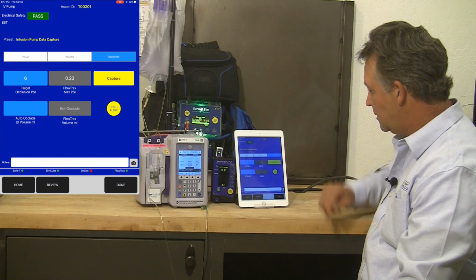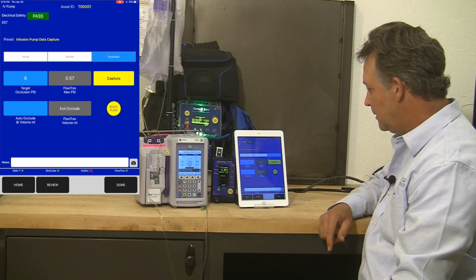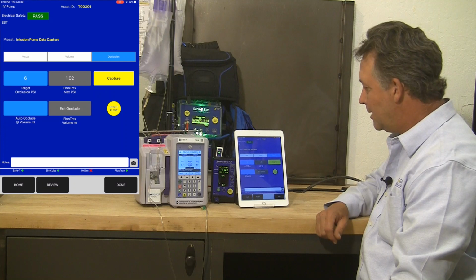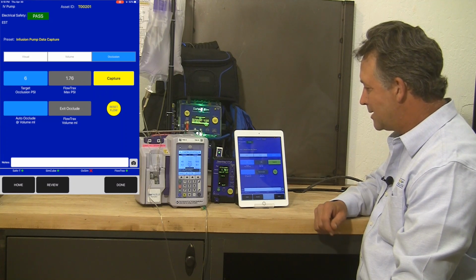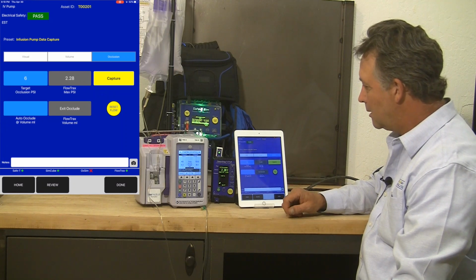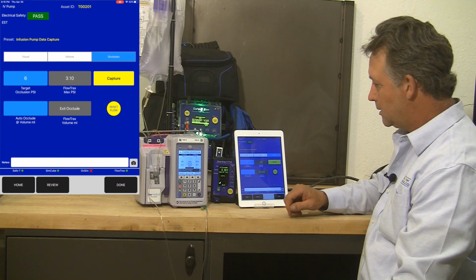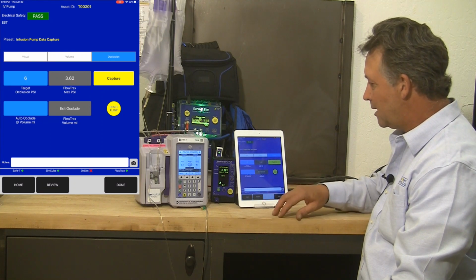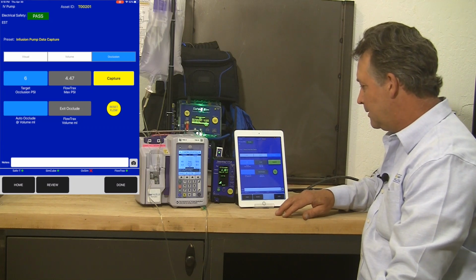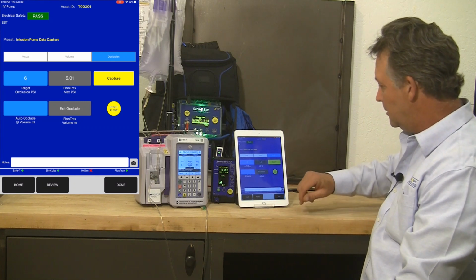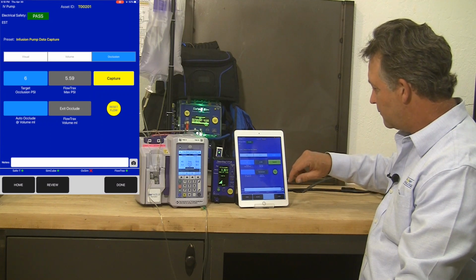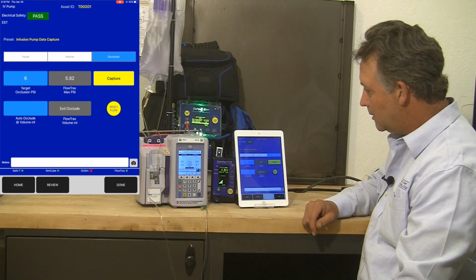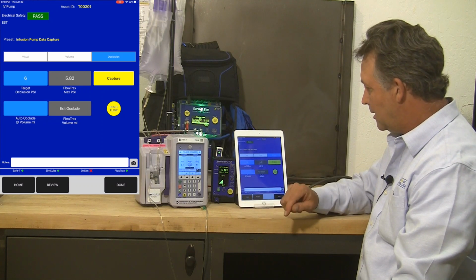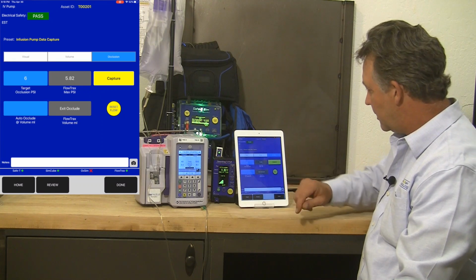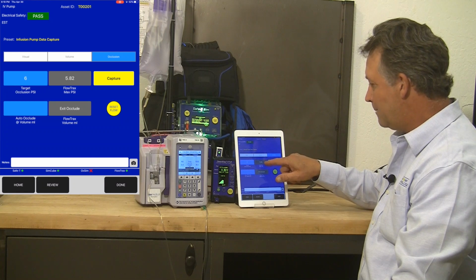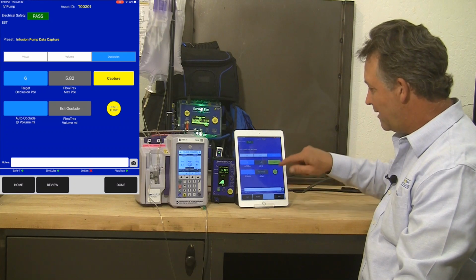I hit the occlude button from my iPhone or my iPad, and we can see the pressure starting to rise. In this case, the target is 6 psi. It shouldn't take more than 10 or 15 seconds for the pump to detect that pressure, as the pressure in the IV set is climbing up to 6 psi. Here we're at 4.5 psi already. So we probably got about 10 seconds before the IV pump detected the alarm. So it knows now that the IV set is occluded. It's alarming at us. We've got the peak pressure or max pressure at 5.82.